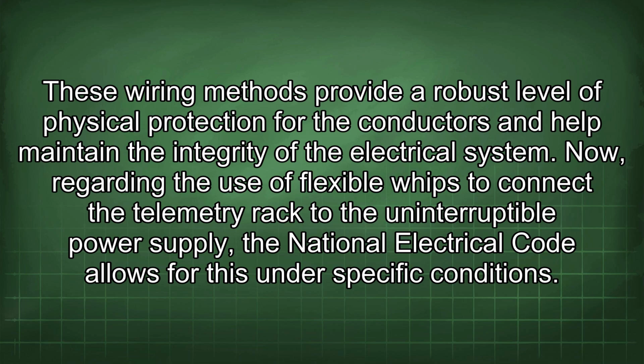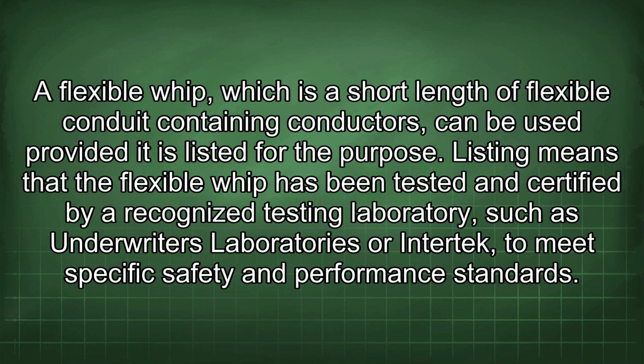electrical system. Now, regarding the use of flexible whips to connect the telemetry rack to the uninterruptible power supply, the National Electrical Code allows for this under specific conditions. A flexible whip, which is a short length of flexible conduit containing conductors, can be used provided it is listed for the purpose. Listing means that the flexible whip has been tested and certified by a recognized testing laboratory, such as Underwriters Laboratories or Intertek, to meet specific safety and performance standards.